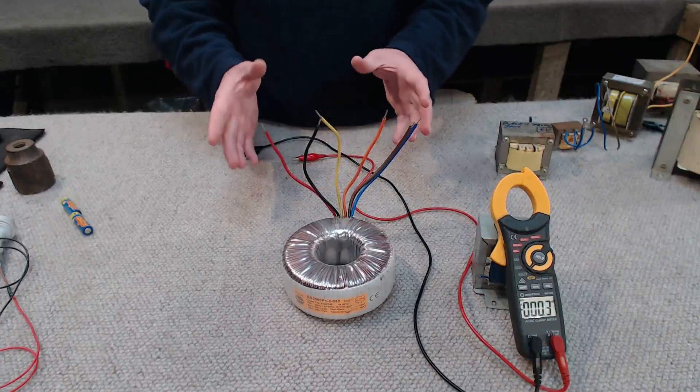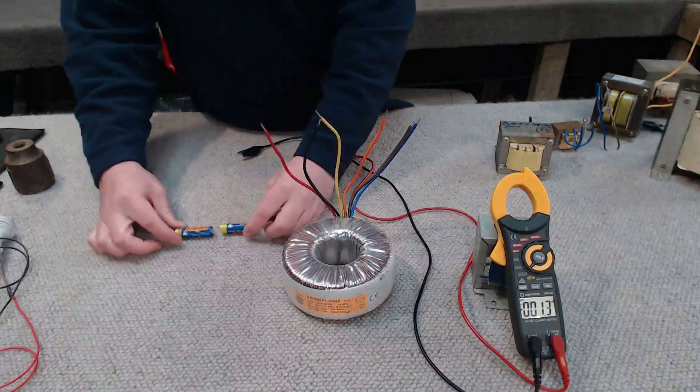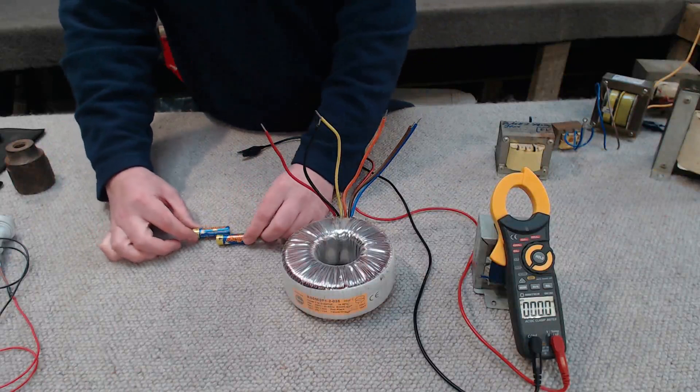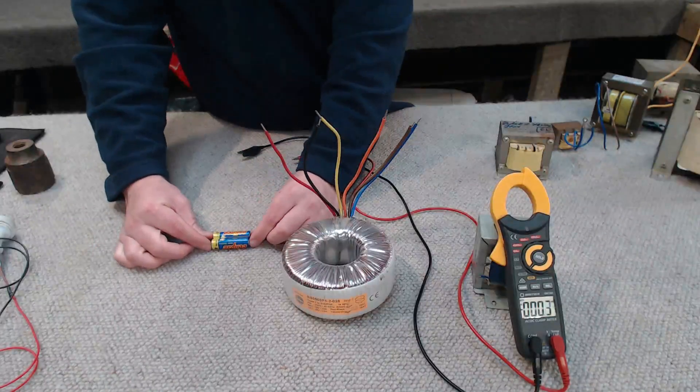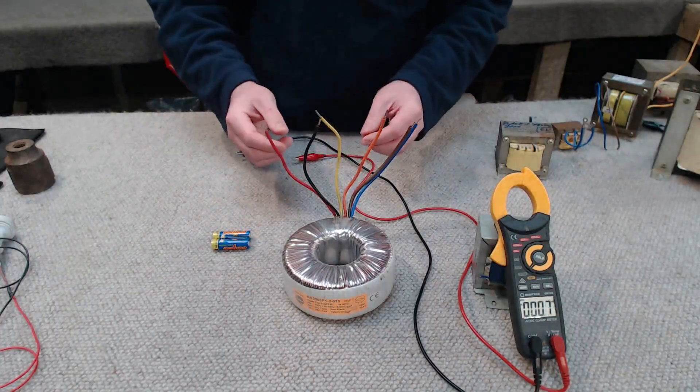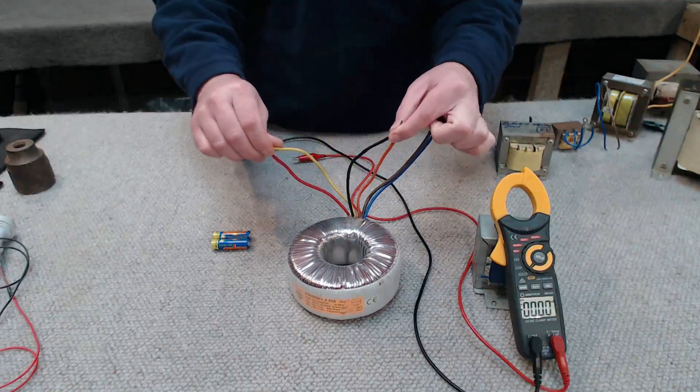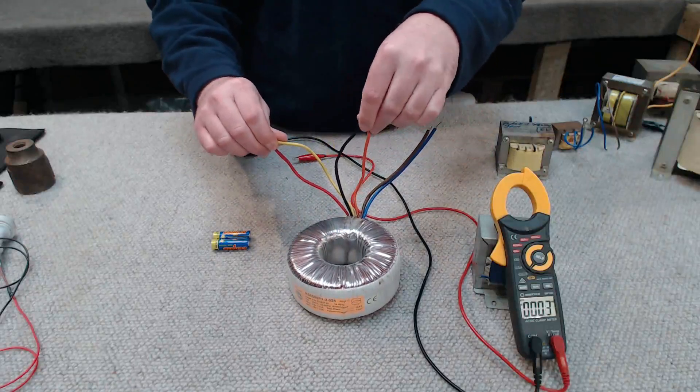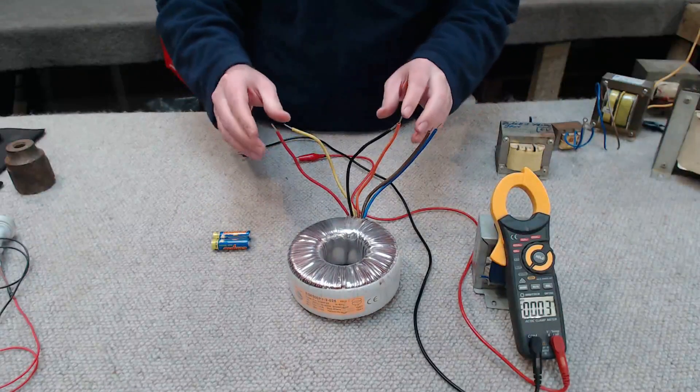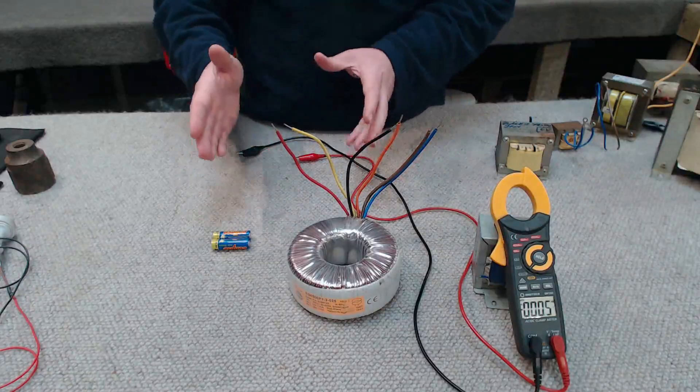There is another way we could configure the secondaries though. We could put them in parallel. So parallel, rather than connecting, if we go back to our batteries, positive to negative, we're going to connect both positives together and both negatives together. So this will not increase the voltage, but it will increase the current. And you'd wire it something like this. We've got orange and black and yellow and red. And this would now be in a parallel configuration where we get 25 volts, but we now get it at 20 amps of current.